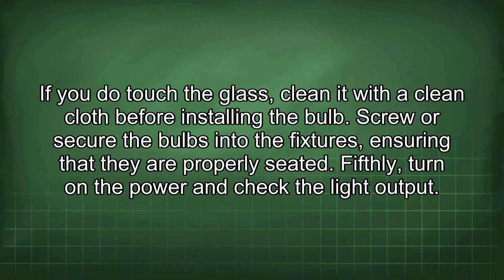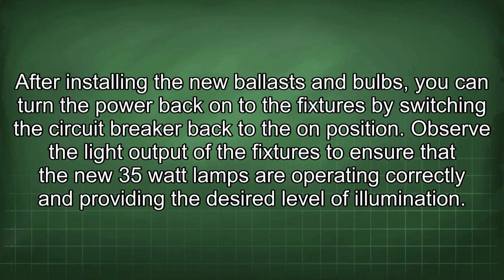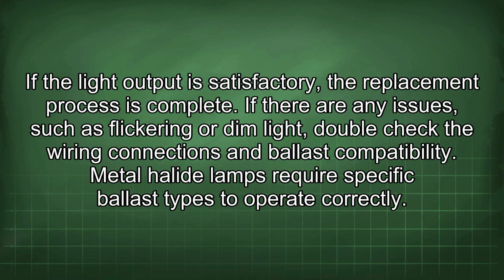Fifthly, turn on the power and check the light output. After installing the new ballasts and bulbs, you can turn the power back onto the fixtures by switching the circuit breaker back to the on position. Observe the light output of the fixtures to ensure that the new 35-watt lamps are operating correctly and providing the desired level of illumination. If the light output is satisfactory, the replacement process is complete. If there are any issues, such as flickering or dim light, double-check the wiring connections and ballast compatibility.